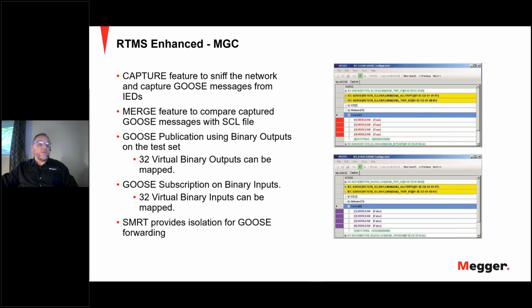The scanning process is known as GOOSE sniffing, and the MGC also provides advanced network troubleshooting tasks, such as comparing the GOOSE messages available on the network with the GOOSE messages described in the SCL files with GOOSE merge compare functionality.